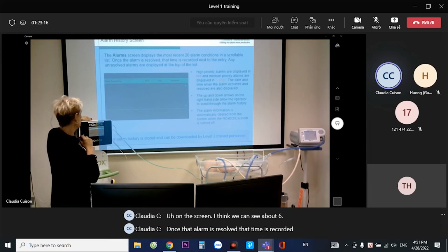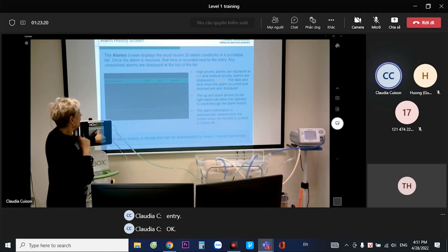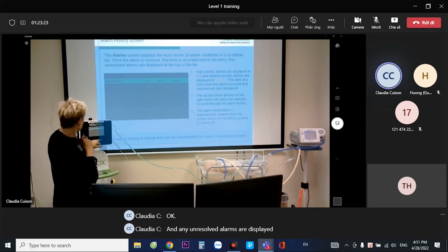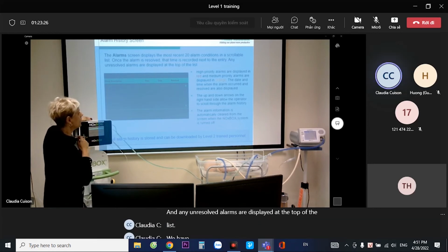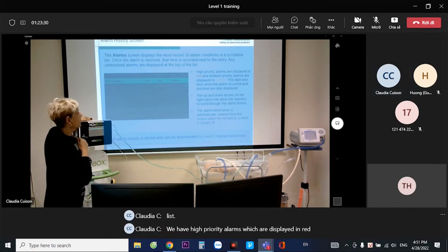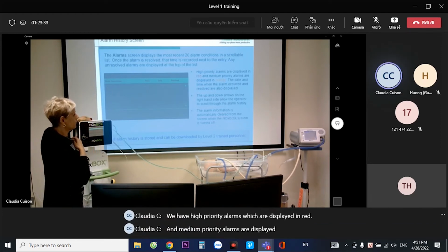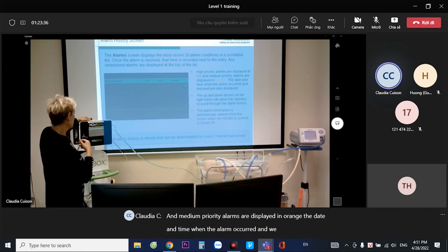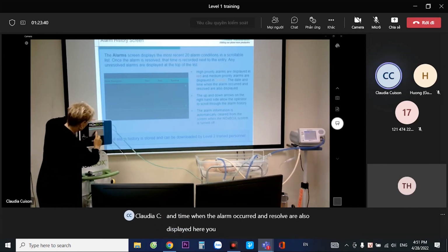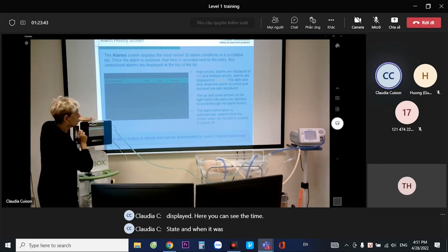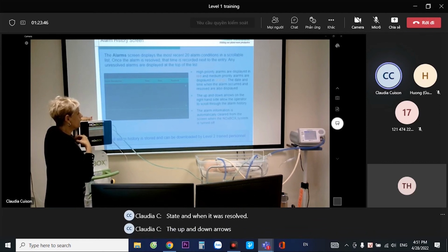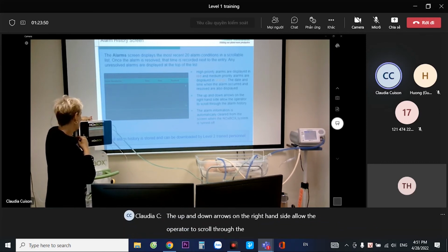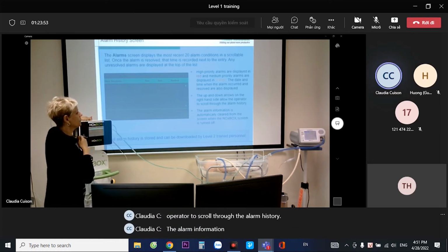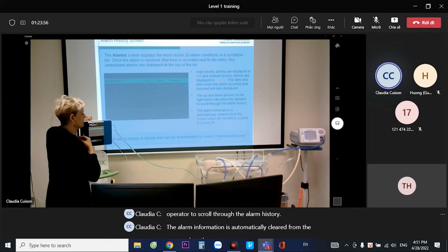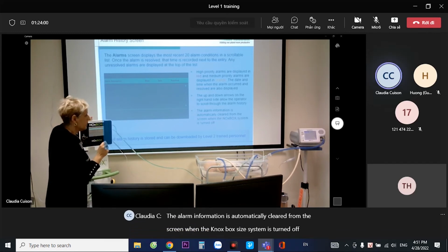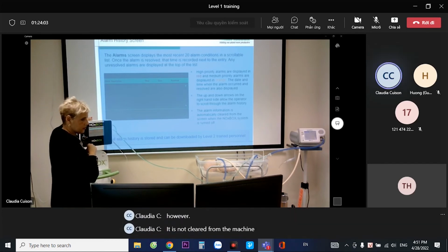Once the alarm is resolved, that time is recorded next to the entry. Okay. And any unresolved alarms are displayed at the top of the list. We have high priority alarms, which are displayed in red, and medium priority alarms, which are displayed in orange. The date and time when the alarm occurred and resolved are also displayed here. The up and down arrows on the right-hand side allow the operator to scroll through the alarm history. The alarm information is automatically cleared from the screen when the system is turned off. However, it is not cleared from the machine.